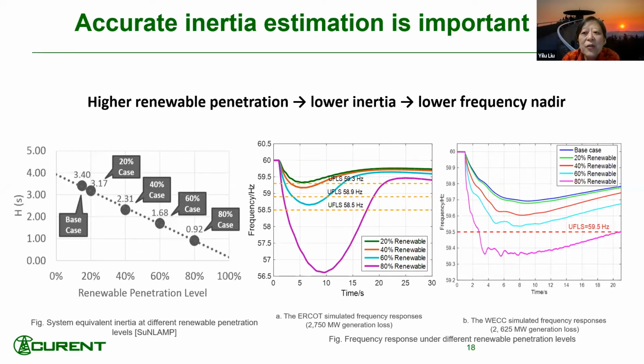And the most fearful thing for the power grid, of course, they worry about blackout, but the realistic fearful thing for any CEO operating the grid is frequency dropping low, because you have very bad publicity, you lose revenue, and also cold pickup load is quite messy. So you can see that you easily get into under frequency load shedding for the ERCOT grid in the middle graph, right? And on the right side, if you get to high renewable in the 80% case, for the Western Interconnection, you cross the line. Anytime you cross the dash line, you have to find a way to deal with it, by some artificial inertia or some other way to deal with the problem.